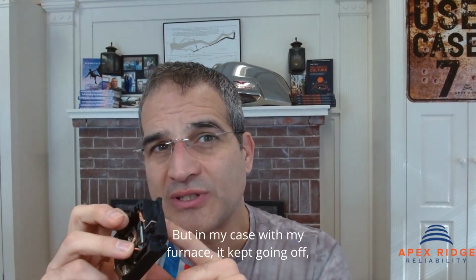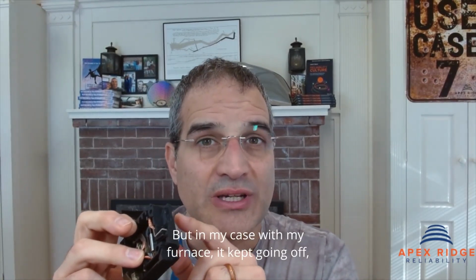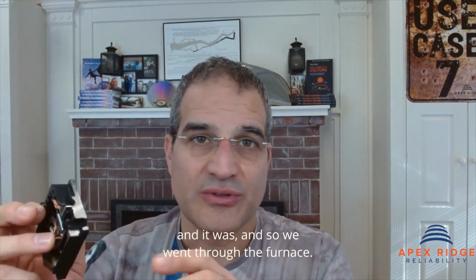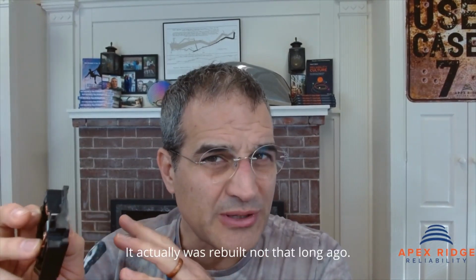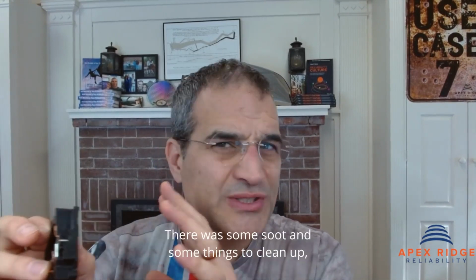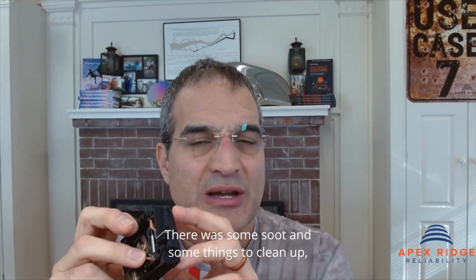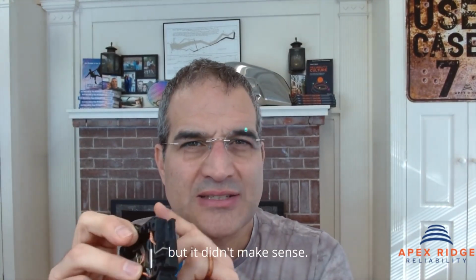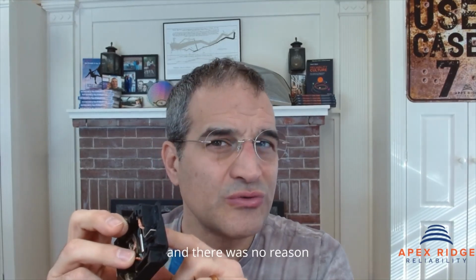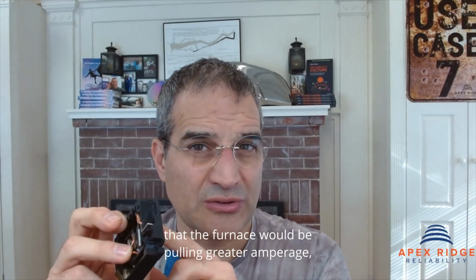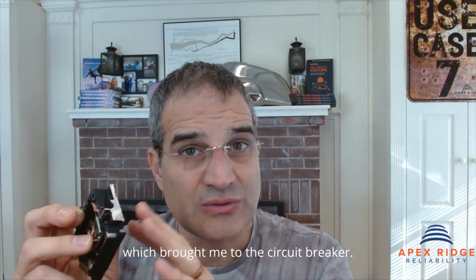But in my case with my furnace, it kept going off. So we went through the furnace, had it maintained - it actually was rebuilt not that long ago. There was some soot and some things to clean up, but it didn't make sense. There's nothing else on the circuit, and no reason the furnace would be pulling greater amperage, which brought me to the circuit breaker.